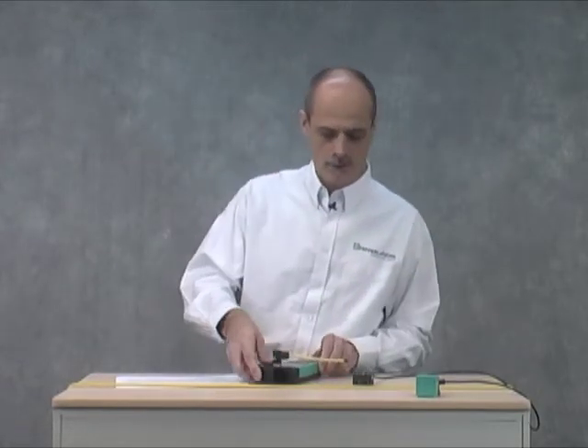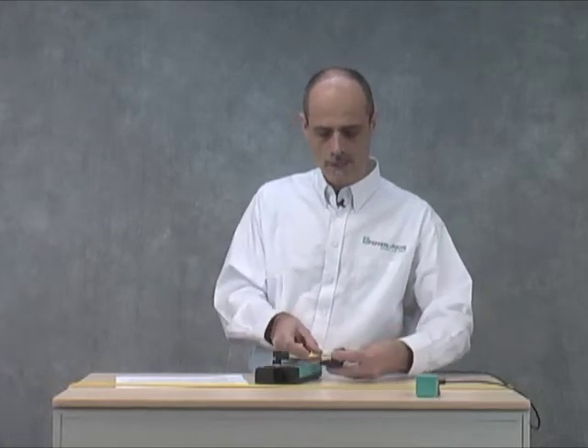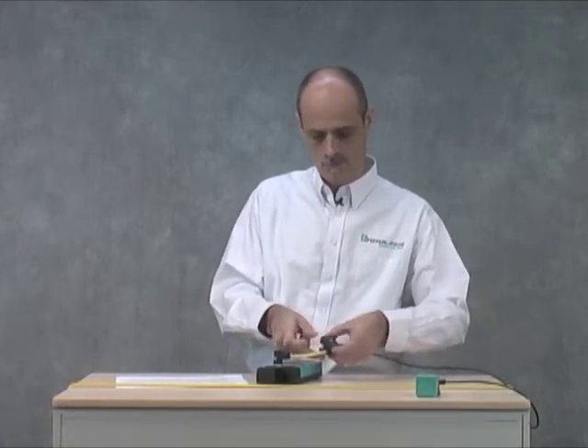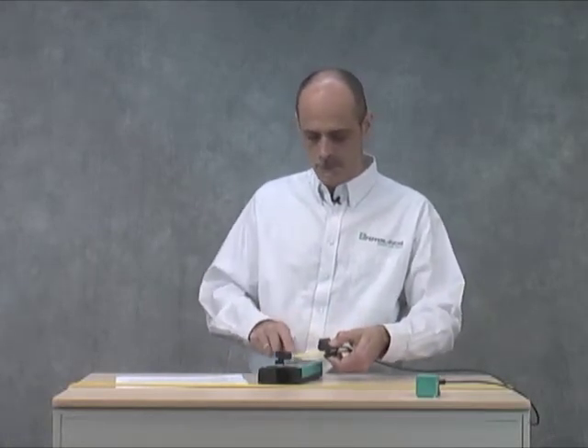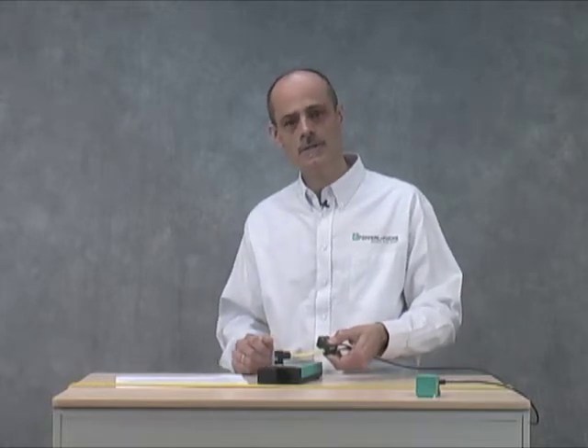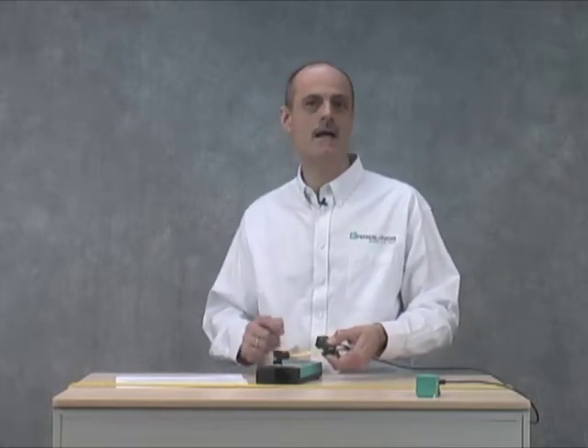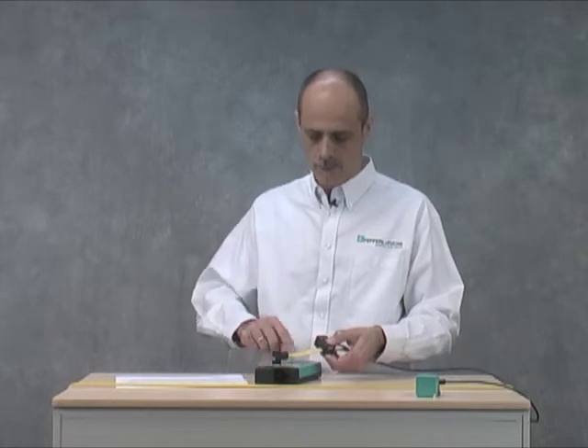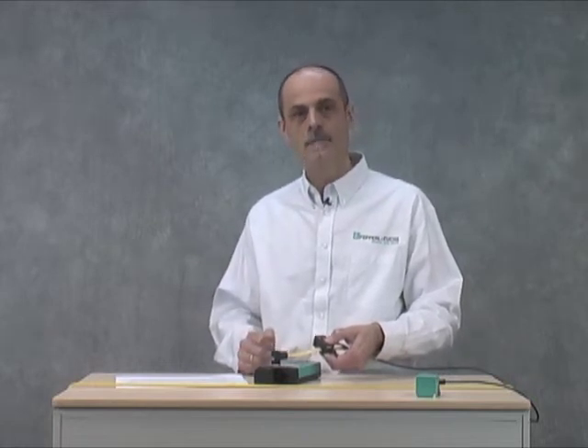Slightly push the module onto the cable. Read the current address, then select the desired new address and program it in. If you are not familiar with the operation of the handheld addressing tool, check out our video at the Pepperl & Fuchs YouTube channel.